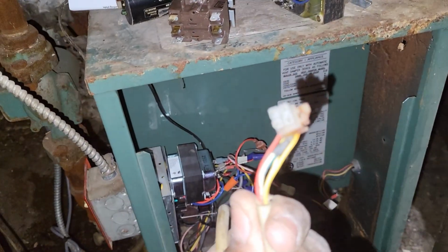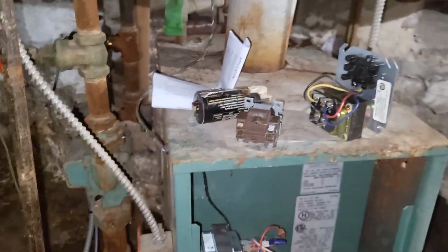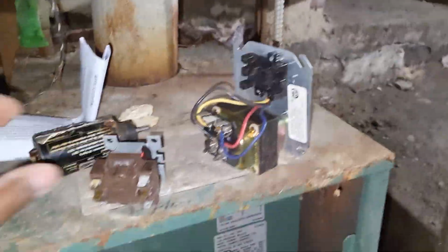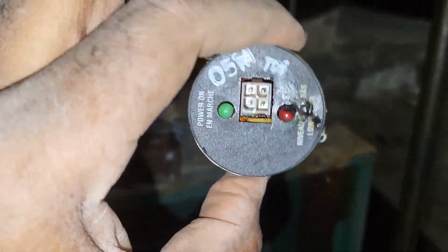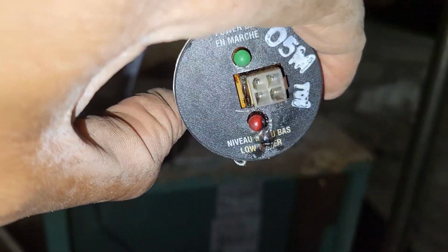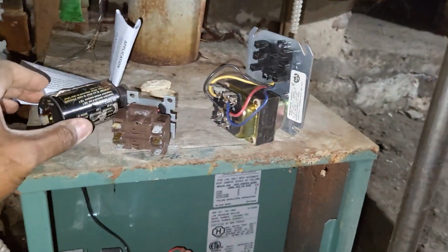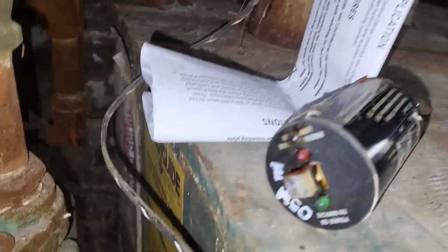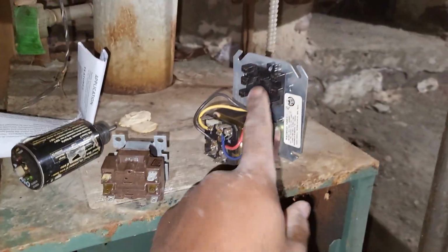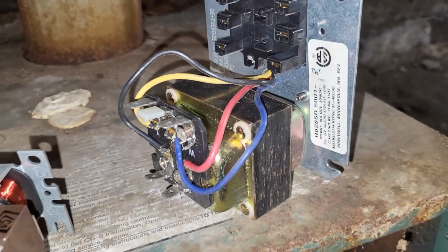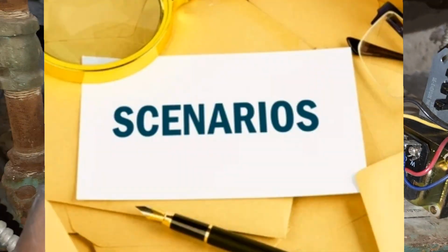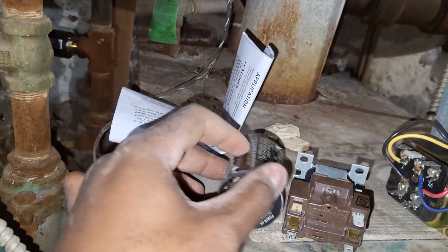And as soon as I looked around the corner, I seen this. And this is definitely a culprit. What happened first or how it happened is none of my concern, but I can only go off of what I see. And if you see everything burnt and melted, make sure you rectify the situation before replacing the transformer. Otherwise, this could have caused the same thing that happened with a new transformer.